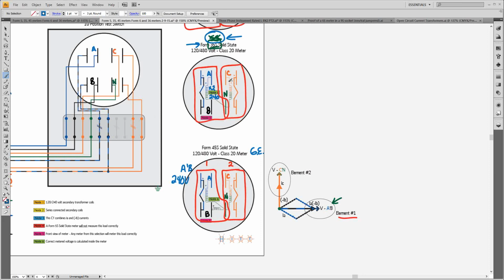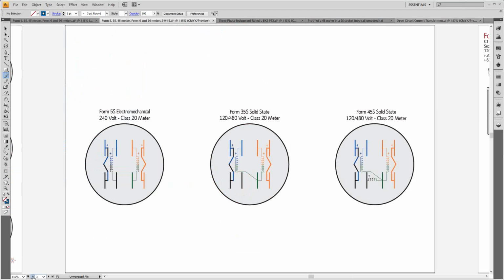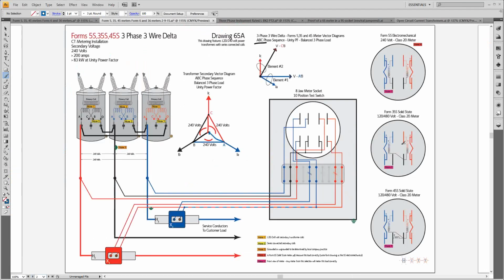Again, if this sees 208 across this potential coil, it multiplies this voltage by 2. Now, when this meter is in 3-phase 3-wire delta, the voltage across this potential coil, because this is B phase, would be C to B voltage, it would be 240. So with 240 there, we'll go back over to that drawing. Just one second here. I'll zoom in a little bit.